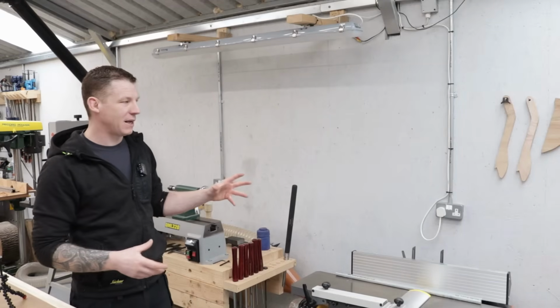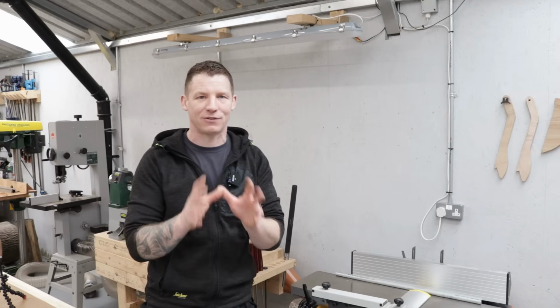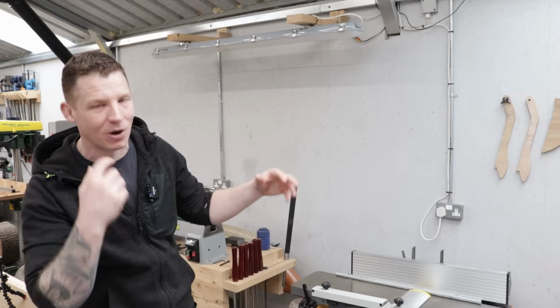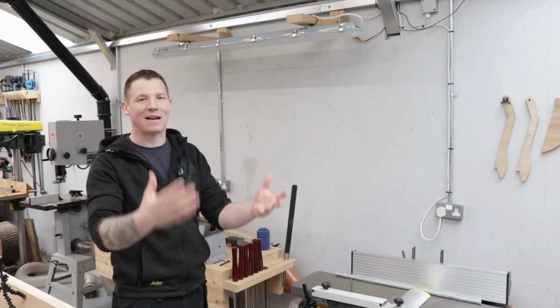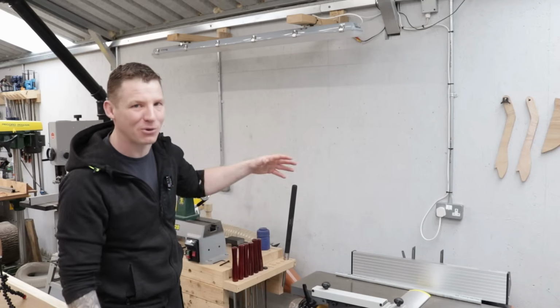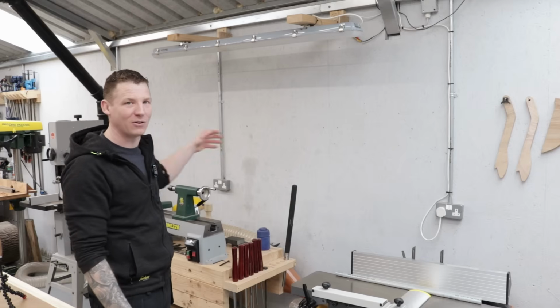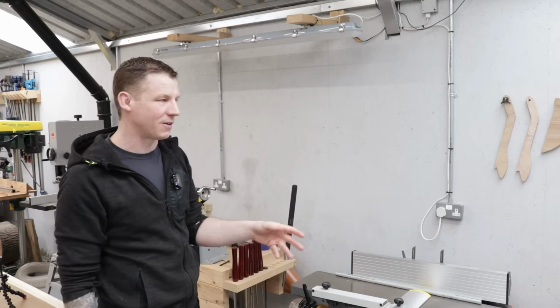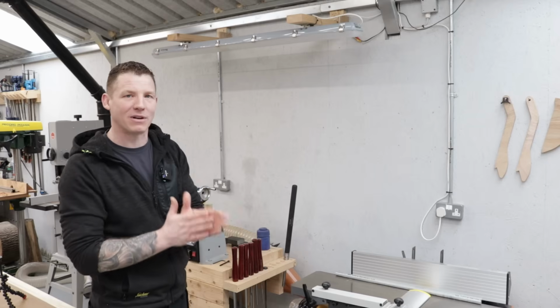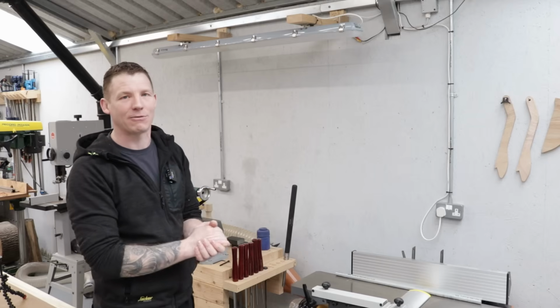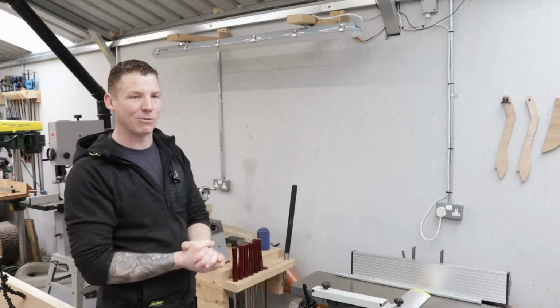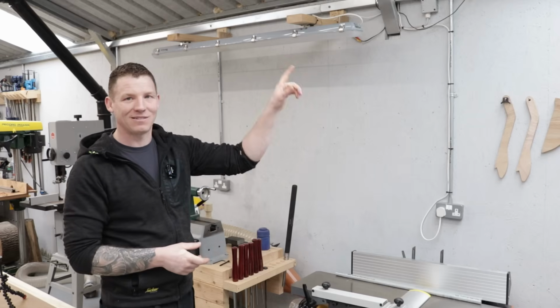Now, I always recommend that you keep plenty of circuits, not plenty of sockets. You want plenty of sockets, but on plenty of circuits. So we don't want to put like 10 sockets or 6, 7 sockets in a workshop all on the one circuit. Again, one thing we have to always remember is that loop impedance, and I'm going to demonstrate that for you, like I said, and I'll explain a little bit more when it comes to the extension leads. So we got to think of the distance of the run.